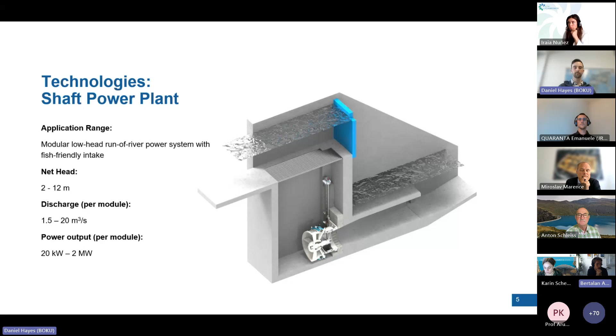The first technology is the shaft power plant, for low head sites. This was developed earlier at my university, and within the Hydro4U project we have brought it to the next level, optimizing the modularity and scalability. Global Hydro Energy, our partner from Austria, has developed a new turbine suitable for this concept. We have optimized both static and dynamic elements to improve it, and now we are proving it at one of our demo sites. The power output per module can be small, from 20 kilowatts, up to 2 megawatts, and this concept is scalable even for much larger sites, up to around 10 megawatts, as you can build several modules in parallel.